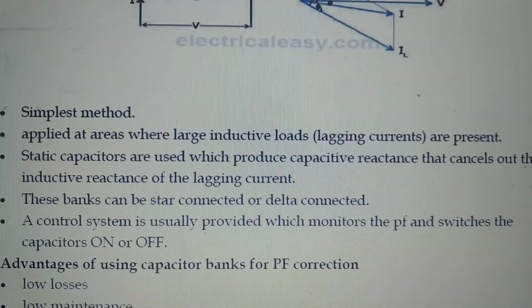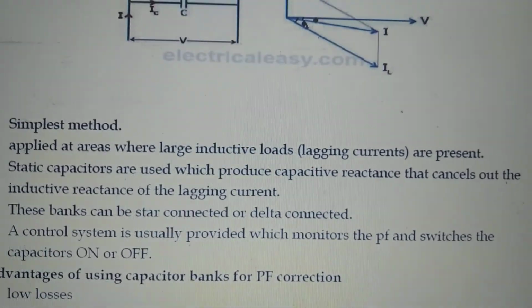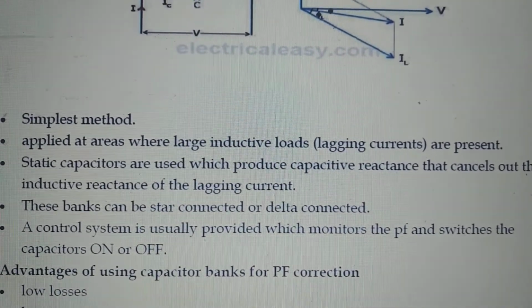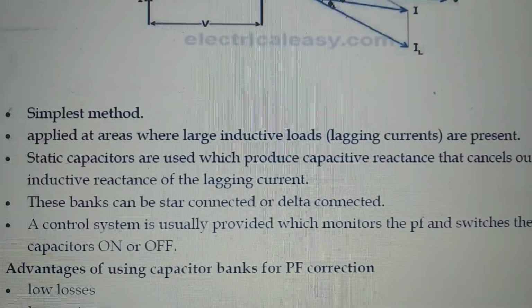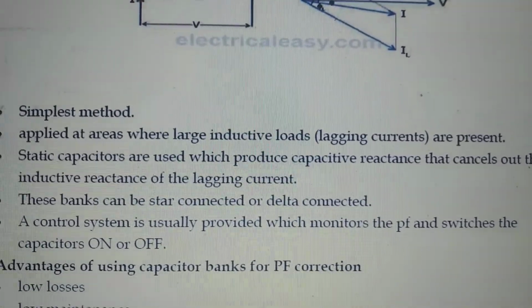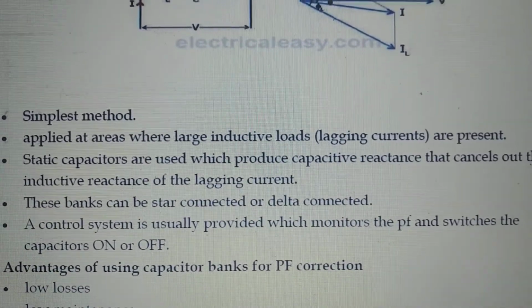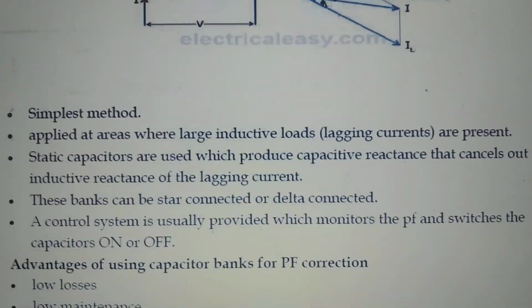Static capacitors are used, which produce capacitive reactance that cancels out the inductive reactance of the lagging currents. These banks can be star connected or delta connected. A control system is usually provided which monitors the power factor and switches the capacitors on and off.